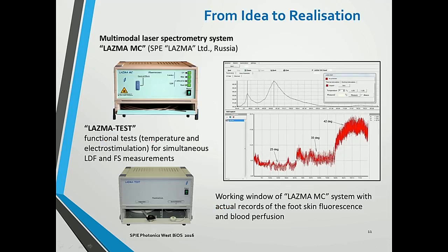And this is how this machine was developed, how it looks. So there are 2 blocks. This is a measuring and monitoring block, which does in parallel measurement of fluorescence in the tissue, where the optical probe is located, and at the same time measures the velocity of blood perfusion in the tissue. And the next block applies different temperatures, operated within the software developed for both of them.